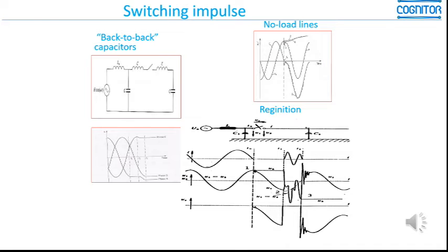And this big overvoltage just after the moment that the circuit breaker is doing the interruption can cause what we call the reignition. If you have the reignition of the circuit, that is, if the current starts to circulate again, you can have a kind of process in which the voltage goes higher, and can lead to the failure of the circuit breaker in this circumstance.